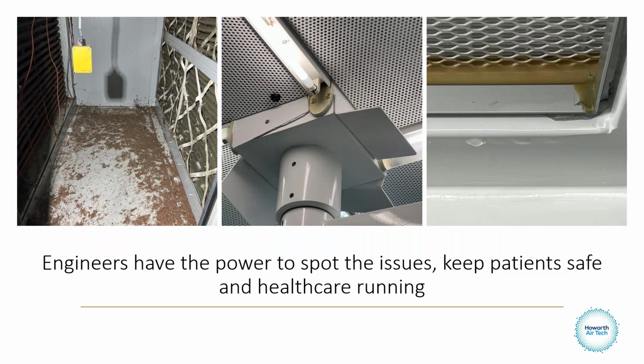And then we continue to look at other things, such as this intake on an air handling unit. We have the capillary there across the frost core, which is fine, that's not a problem. This hanging electrical thing here is a problem, and I have no idea what this is - that's a problem. And then the pigeon that's been dragged through the air handling unit, that's a problem. So again, this has been called up for verification. This is ready to be serviced and inspected, and it's obviously disgusting and not up to scratch.